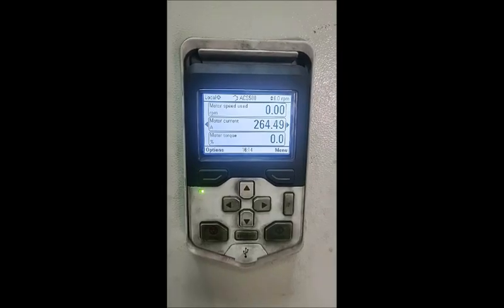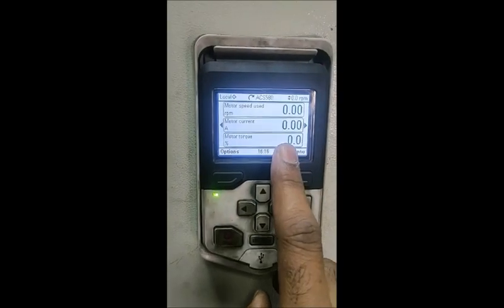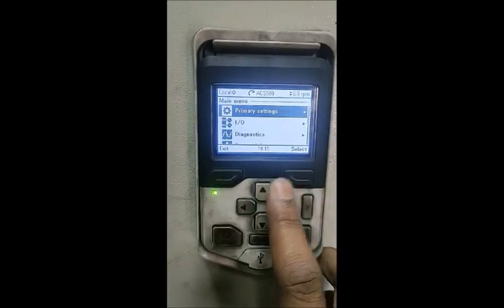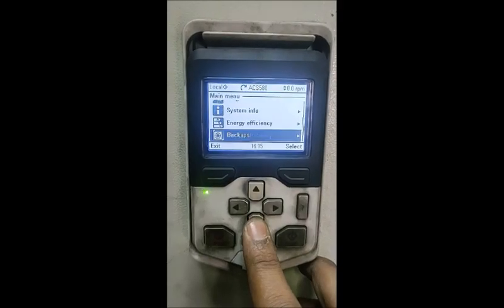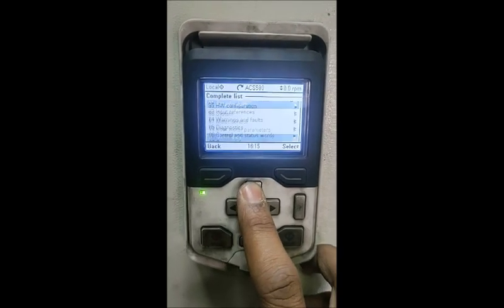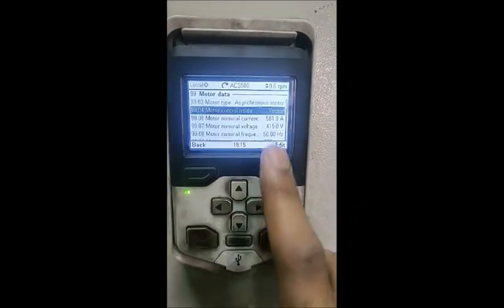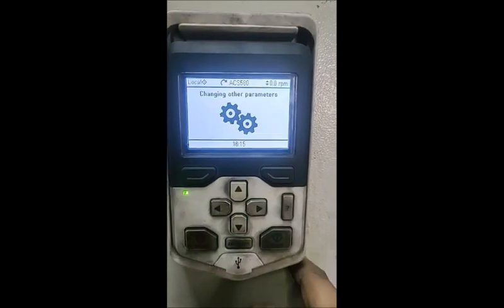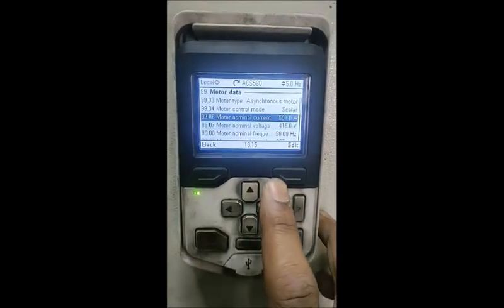Why is ID run performed? There is a separate video on that — I will post the link. The ID run is done; it won't take more than a minute. After that, we will check all the parameters once again. The process is the same: menu, go to parameters at the bottom. One major difference is 'ID run requested' — it has to now show none. Motor data, parameter number 99 — we can see all the values. We can bring the motor control mode back to scalar and save it, or keep it as vector as per the requirement.